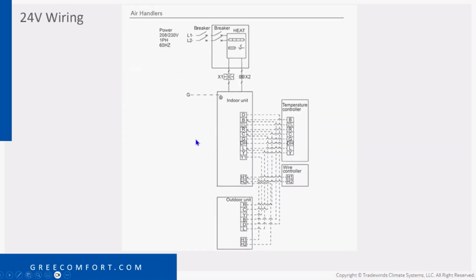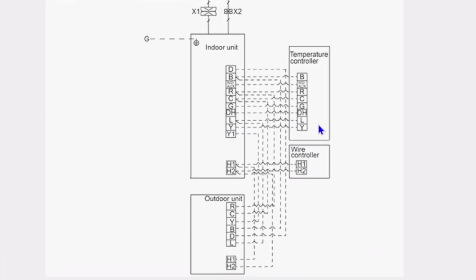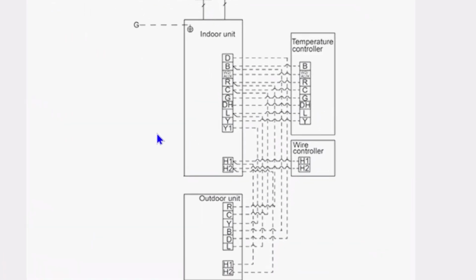to the 24 volt. Now, this is showing the wired controller and the temperature controller. I guess you could do that where you could have the wired controller hooked up and the regular thermostat. More of that will be answered in the instructions that come with the controller, because we have not gotten any of the controllers in yet, so I don't have the instruction manual just yet, and we're waiting on GREE to get us that information. Like I said, there may be advantages to having the wired controller hooked up and a 24-volt thermostat, because there may be advantages as to what we can do with this controller once we get the manual.